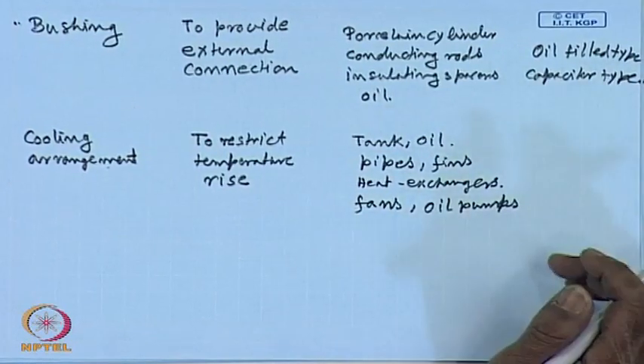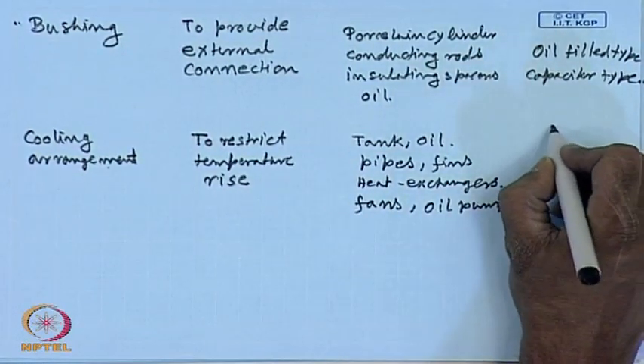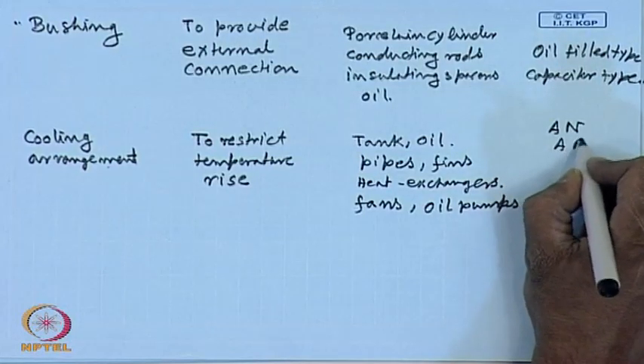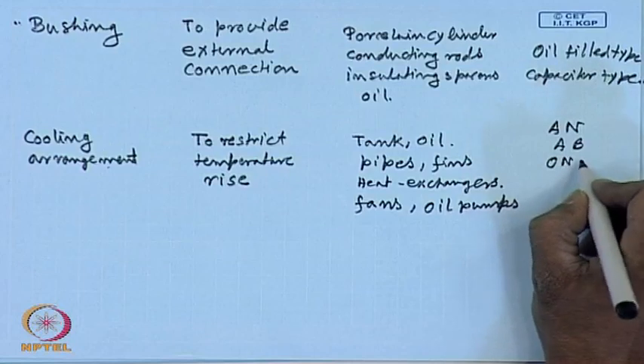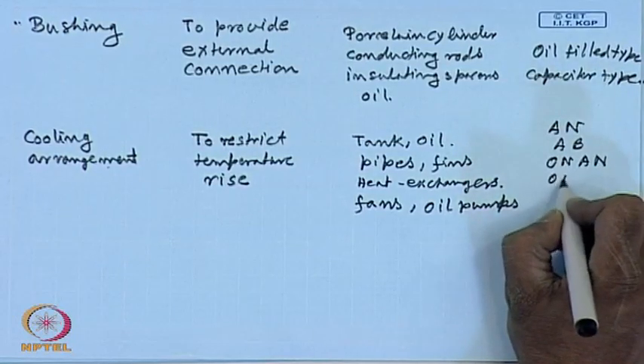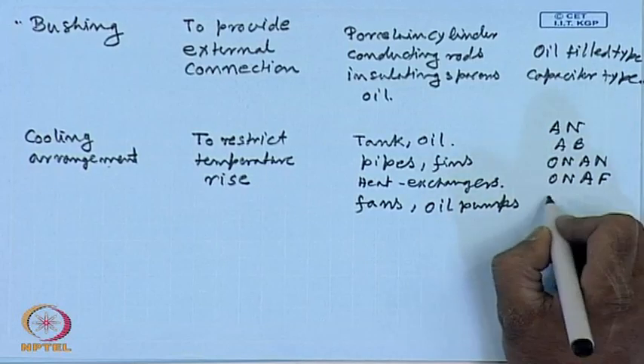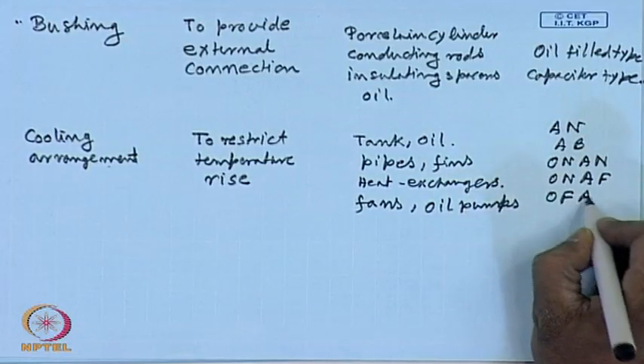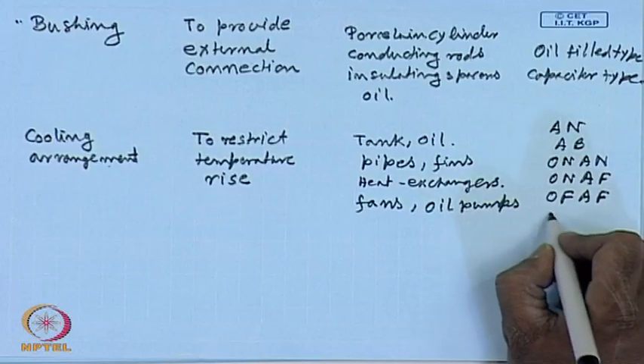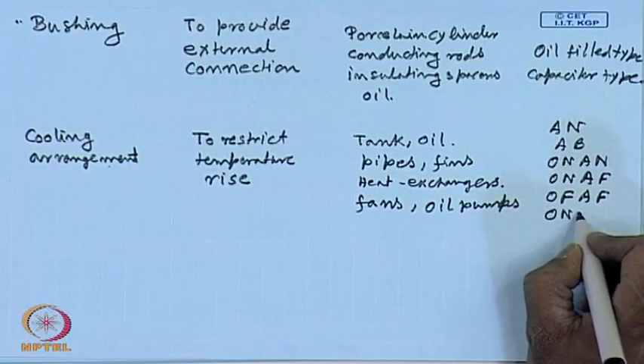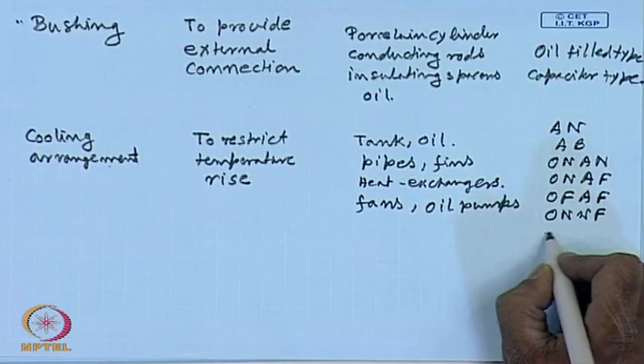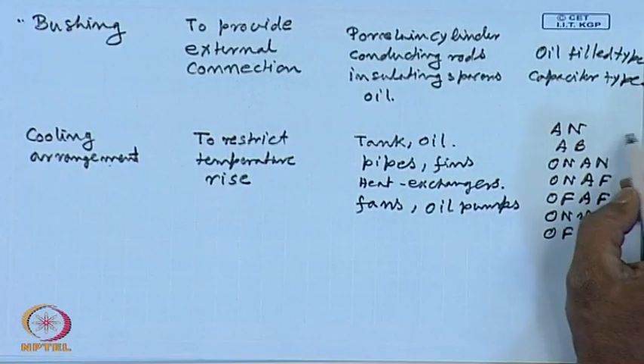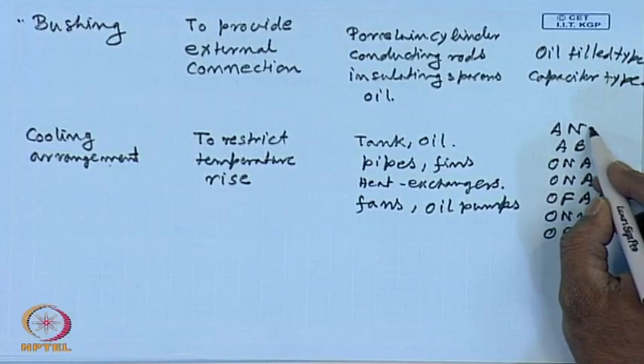These are the components required for the cooling arrangement, and you have different types of cooling. For example, air natural, air blast, oil natural air natural, oil natural air forced, oil forced air forced, oil natural water forced, oil forced water forced. These are different types of cooling. They are used with increasing rating of the transformer. This is for the lowest rating, this is for the highest rating transformer.